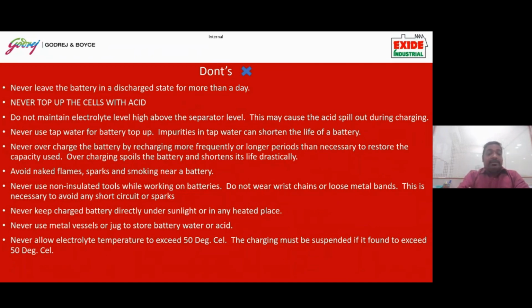Do not maintain the electrolyte level above the separator level. This may cause acid spill out. So a moderate electrolyte level should be maintained. If the electrolyte level is too high in the cell, this will also cause spillage during movement of the forklift. Another very important thing, never use any other water than DM water, because tap water has a huge content of impurity. And if this tap water is poured into the electrolyte, immediate chemical reactions might happen, and it can even lead to conditions like cell burst or blast. This will also completely damage the positive and negative plates and erode the battery and cause failure in a very short span of time.